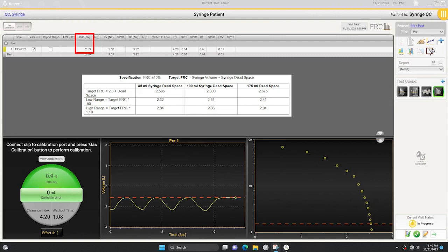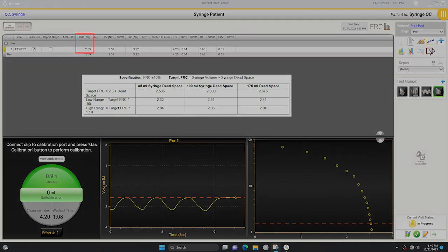If the FRC is not within range, perform another gas analyzer calibration and repeat the effort.